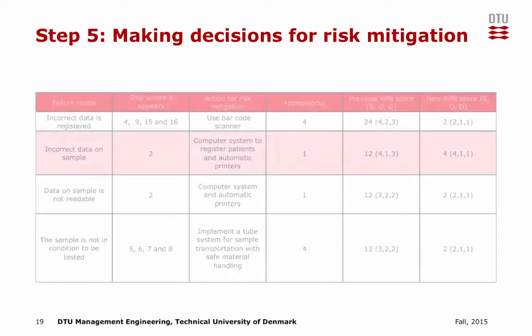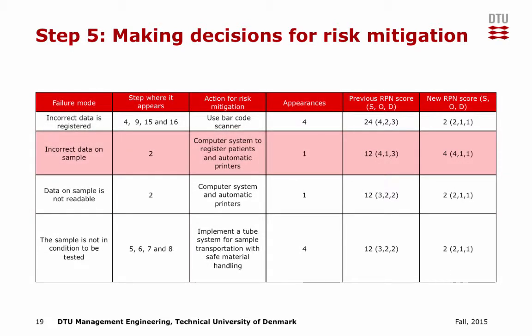In step 5, the decisions for risk mitigation are made. Taking the second failure mode — incorrect data on sample — as an example, the action for risk mitigation is to make use of a computer system to register patients and have automatic printers. This avoids direct human interaction with the transfer of data, reduces the RPN score vastly, and the new score becomes 4.